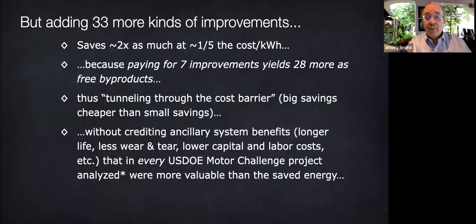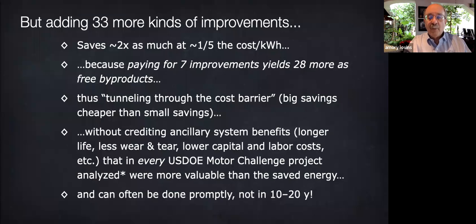And this takes no credit for side benefits that are generally worth more than the energy savings. Moreover, this bigger, cheaper saving doesn't have to wait for routine motor burnout, but can often be profitable to do immediately, increasing its present value. Normal practice, of course, is to wait till the motor fails on the assumption that efficiency gains that might justify the efficient replacement's marginal or extra cost would not normally justify its assumed total cost, although actually we're going to buy it anyway later, so it's really a discounting question.